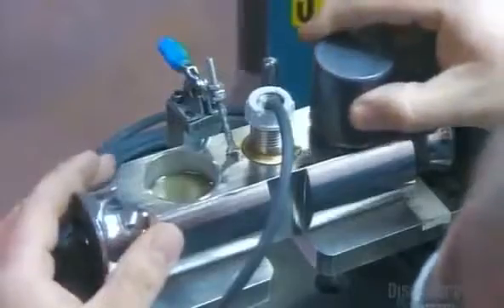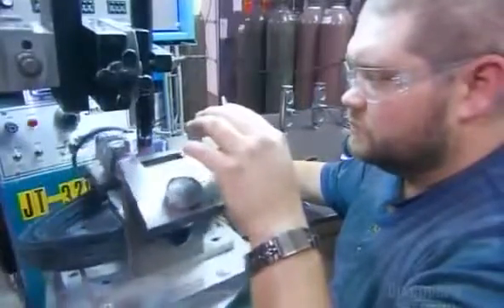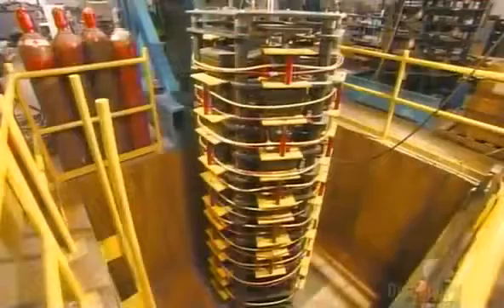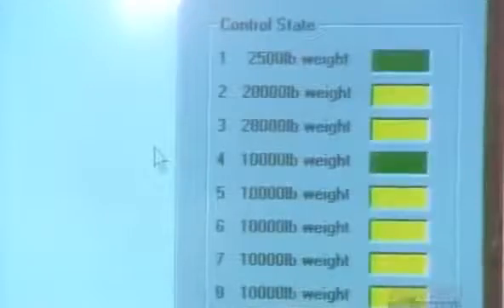The smallest amount of moisture or dirt would cause a strain gauge to malfunction, so they weld a cup over each one to hermetically seal it within the load cell. Every finished load cell undergoes a quality control check, and the testing machine applies weight in increments until it hits the maximum — 34,000 kilograms or 75,000 pounds.